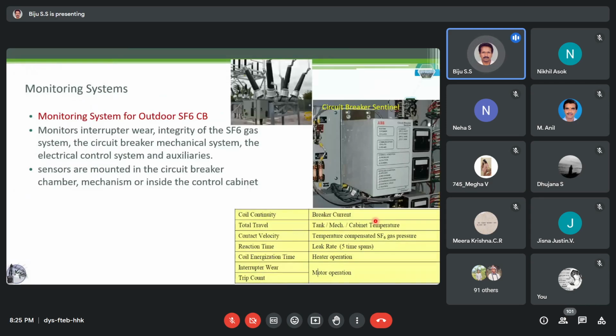Now this is for outdoor SF6 circuit breaker monitoring. In outdoor SF6 circuit breaker monitoring, it monitors the interrupter wear. Again, the contact wear indicator will be there. The integrity of the SF6 gas system will be monitored. The circuit breaker mechanical system will be monitored. The electrical control system and auxiliaries will also be monitored. The sensors will be mounted in the circuit breaker chamber. This is a typical example of an SF6 circuit breaker monitoring system. Breaker current will be monitored. Total travel will be monitored. Contact velocity, reaction time, coil energization time, trip count, etc.